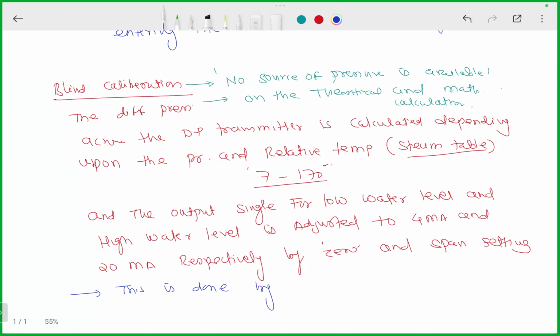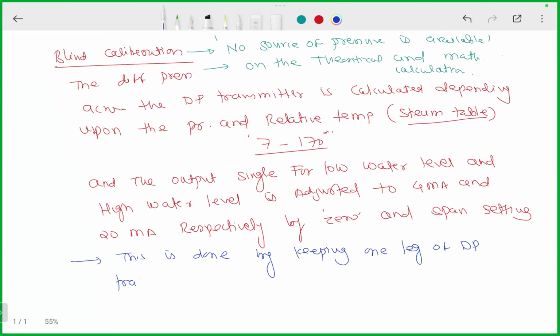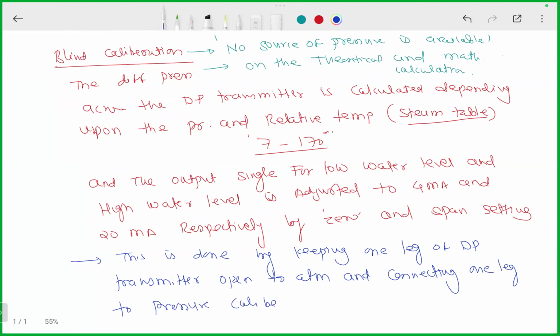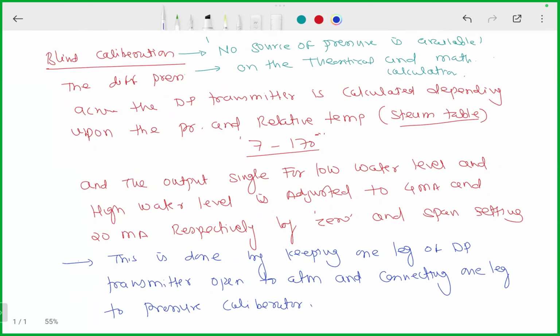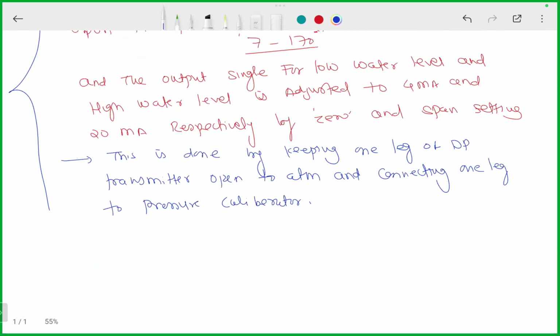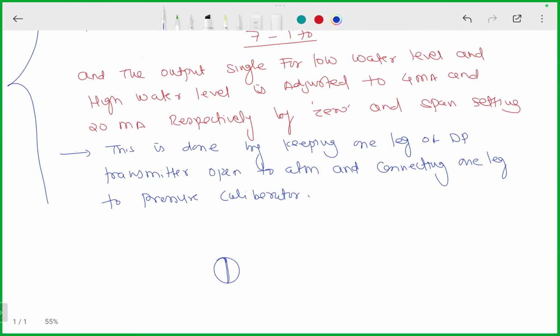This is done by keeping one leg of DP transmitter open to atmosphere and connecting one leg to a pressure calibrator. So the mathematical calculation: the reference leg will be open to atmosphere, and the other leg is connected to the pressure calibrator.